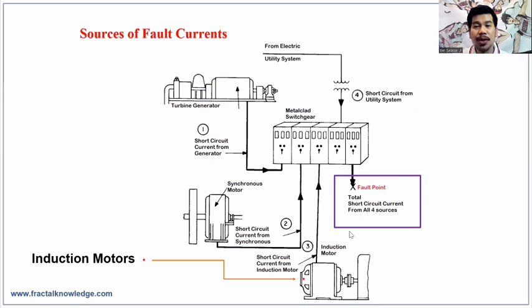The fourth source is induction motor, similar to what I mentioned about the synchronous motors. The induction motor acts as a generator at an instant from 0 to 3 cycle of the sine wave. You may say this has no impact. If that's what you believe in, then you are not an electrical practitioner. If you have lots of induction motors in a given plant and when fault happened, you will wonder at an instant where those fault energy came from. In a transient level, induction motors contribute a lot.